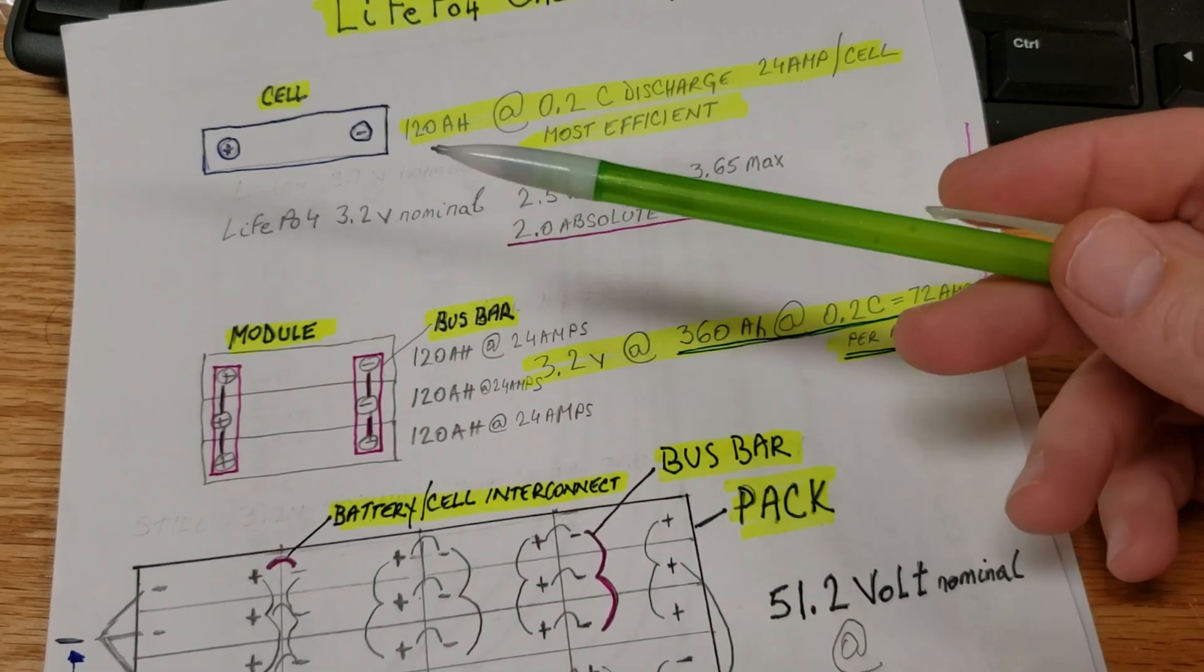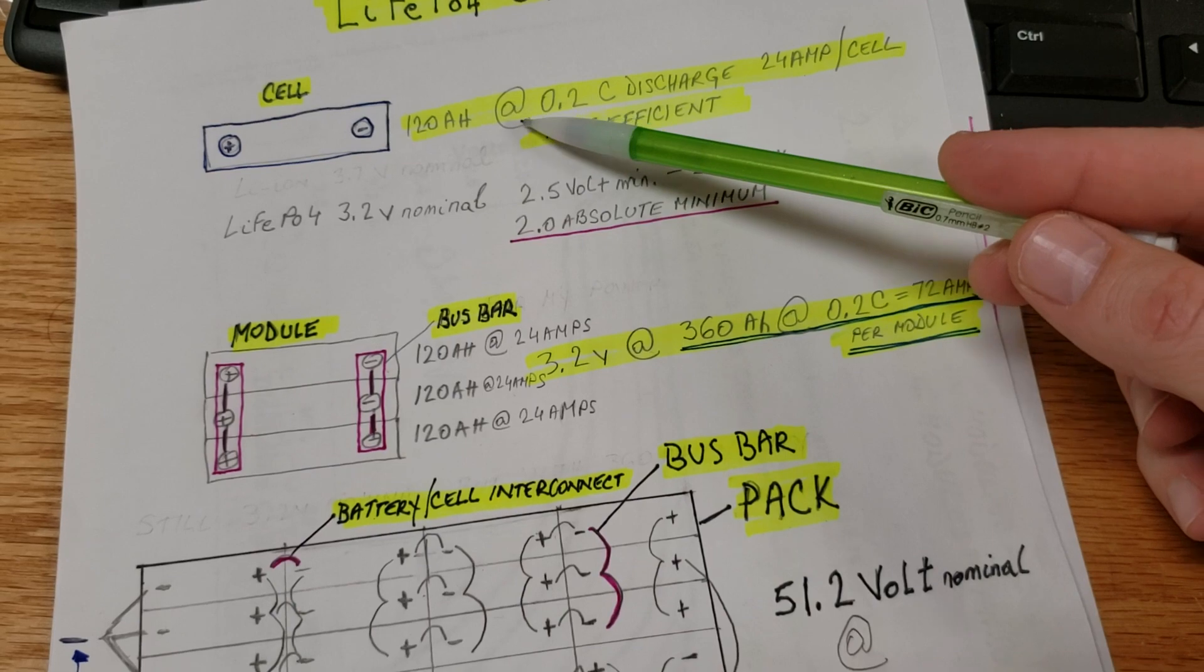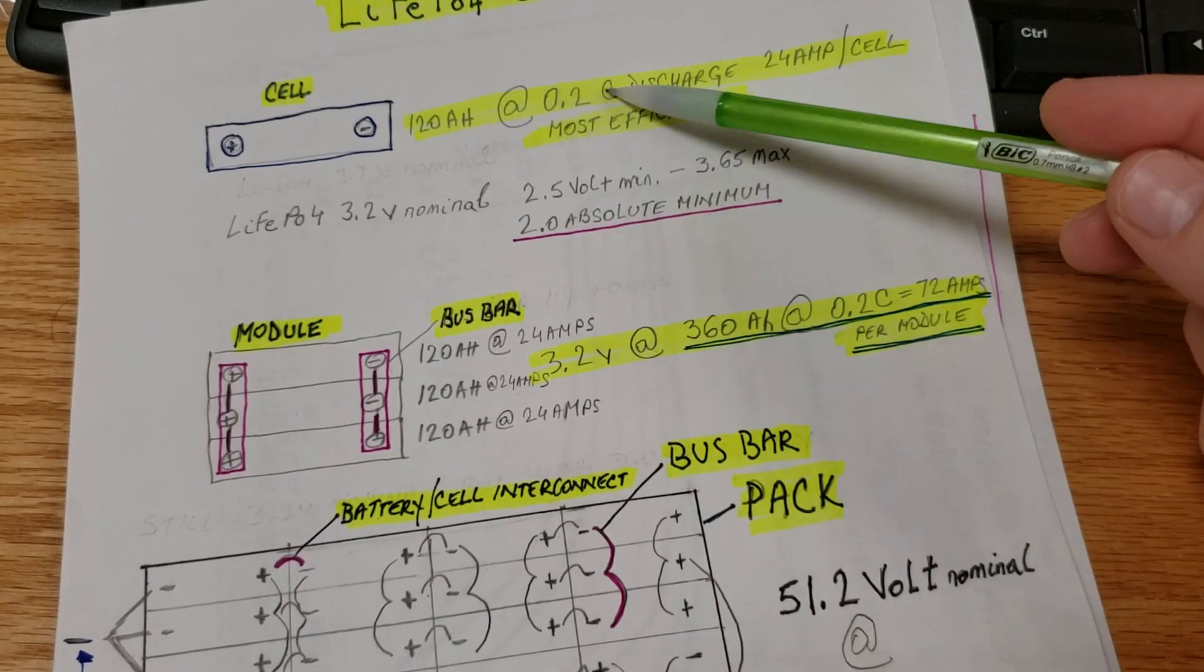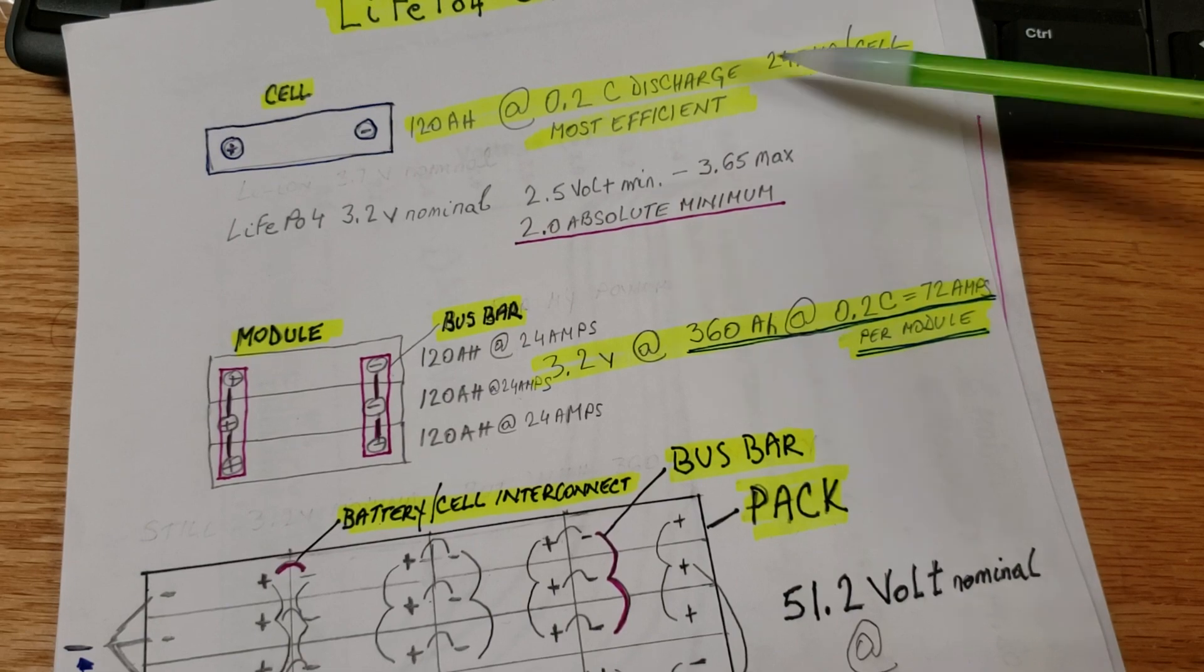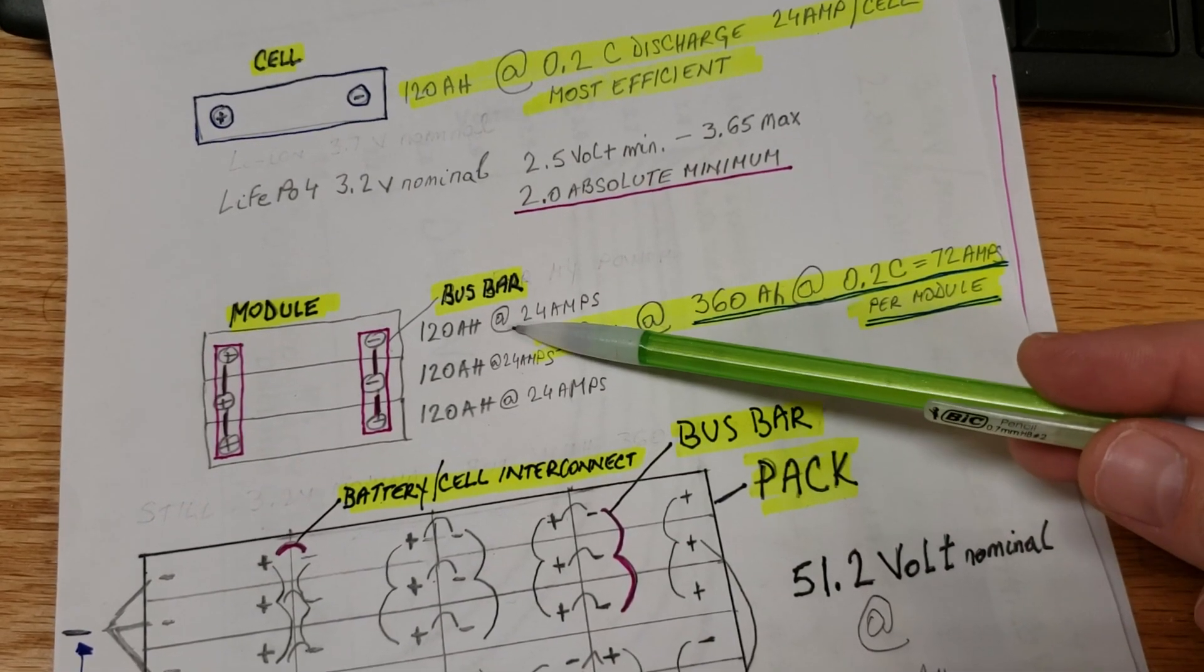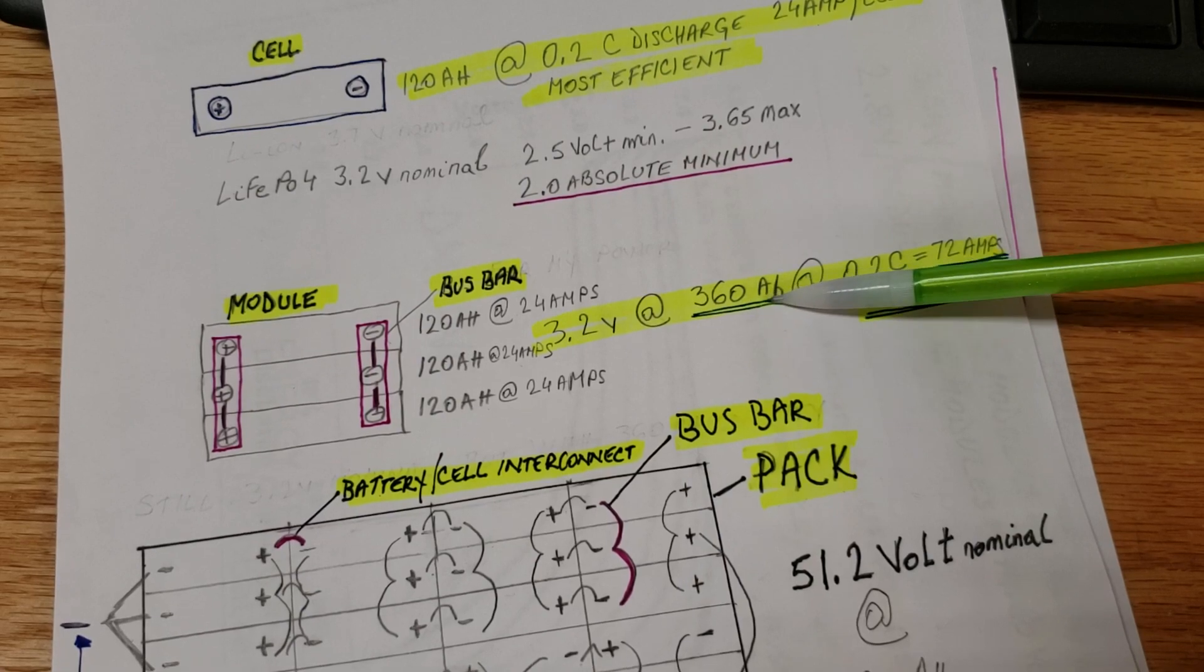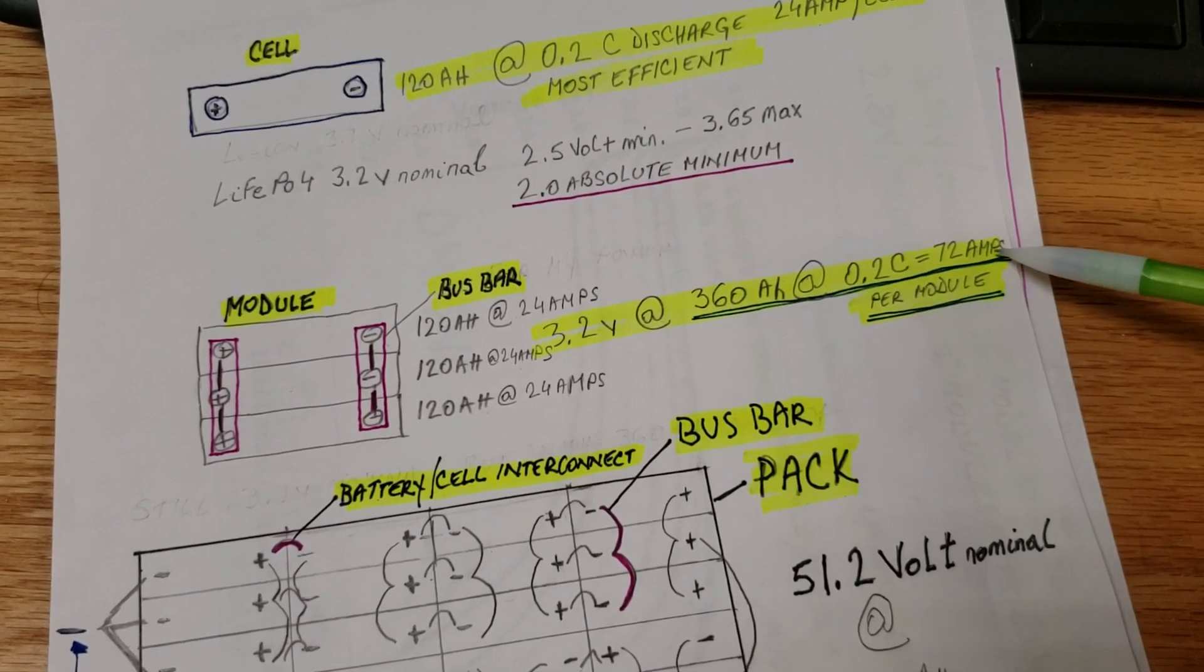Here's the information for the cell and the module. Each cell is 120 amp hours. We will explain in the chemistry charge chart for the lithium iron phosphate battery. The best performance is at 0.2C discharge rate, which for my cell would be 24 amps per cell, most efficient. For the module, we have three cells connected in parallel, meaning you are adding the amperage of those cells. Three cells at 120 amp hours each gives us total of 360 amp hours at 3.2 volts, at the nominal discharge rate of 0.2C, that is 72 amps per module.